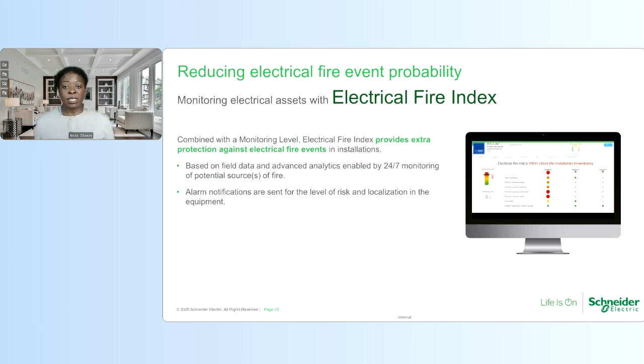So for facility teams, fire risk isn't just a safety concern, as you know, it's a business continuity issue. Downtime, damage, and liability can all stem from electrical faults that go undetected until it's too late. And that's where Schneider Electric's Electrical Fire Index comes in. This is a powerful example of how we can take all of the analytics generated from continuous monitoring and turn them into actionable insights, specifically focused on fire prevention. Our Electrical Fire Index combines real-time monitoring data with advanced analytics to assess the risk level of electrical fire across your assets. It doesn't just alert you, it localizes the risk, prioritizes it, and helps your team take immediate action before the fault becomes a fire.